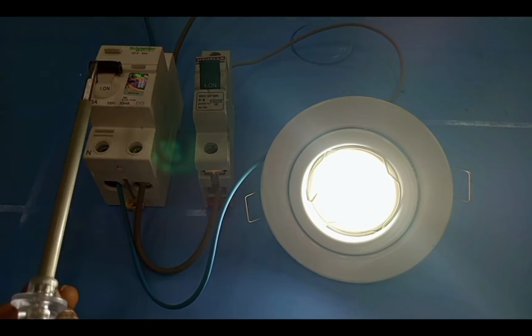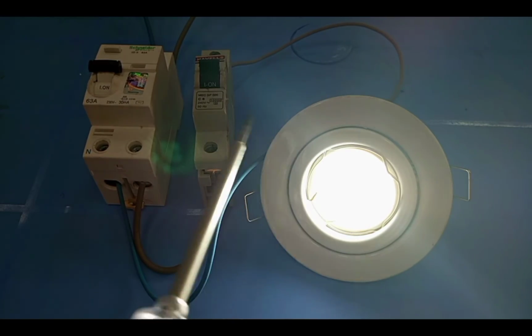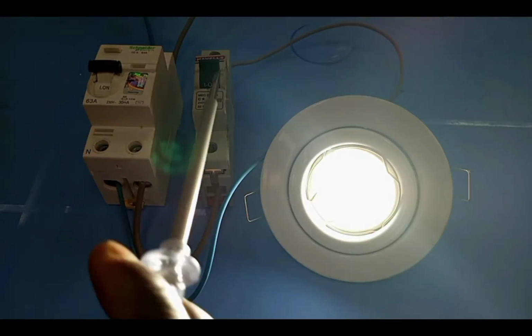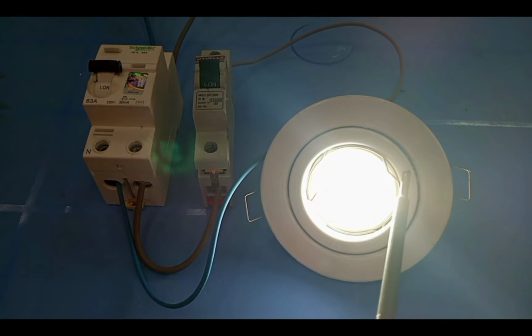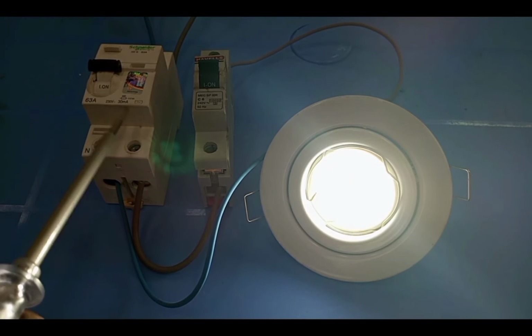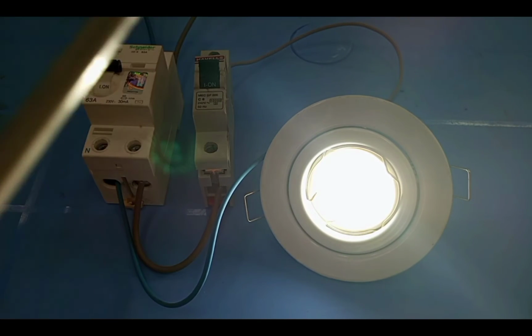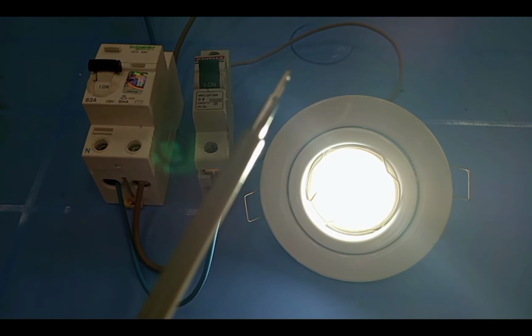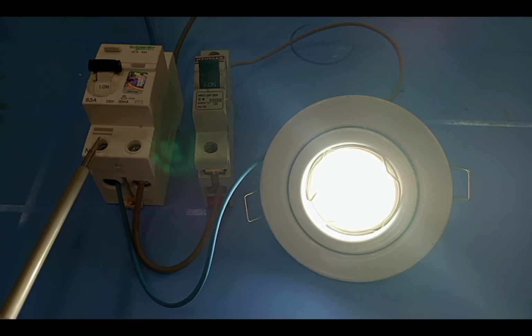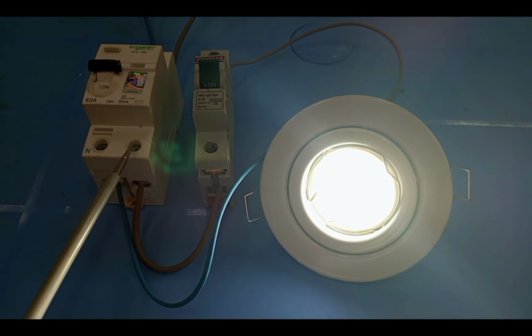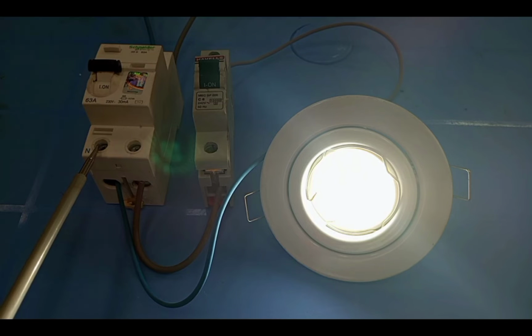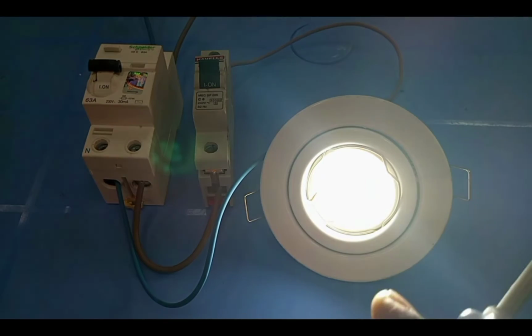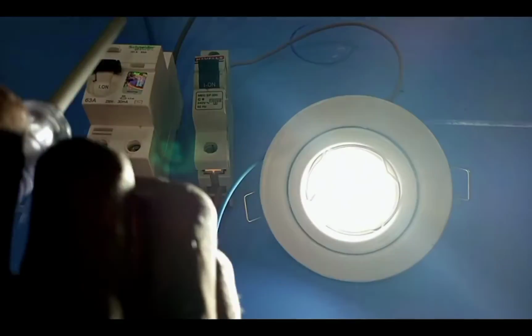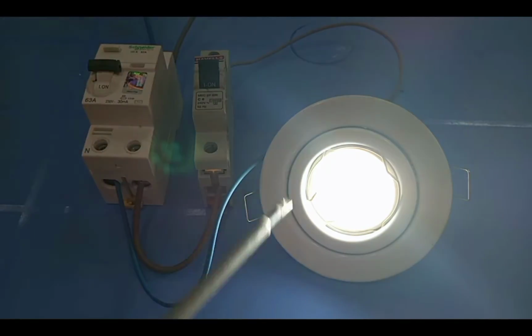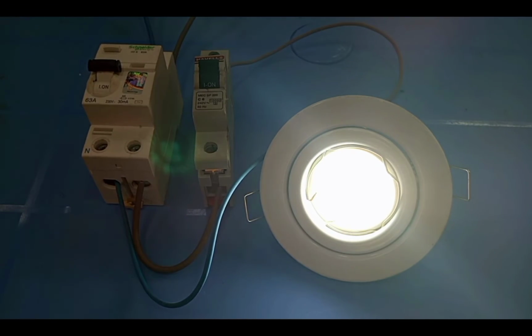Okay. So if I want to connect another load to this load, because it's 6 amps, this one is taking just about 0.02 amps, so I can connect additional load to the same RCD. If I am doing that, then I have to make sure that whatever load I connect, I must connect both the live and the neutral from the output of the RCD. If I connect both live and neutral from the output of the RCD, then 0.02 amps plus 0.02 amps is what must flow through this RCD, through the live and then back through the neutral wire. All right, so let's see how that happens.